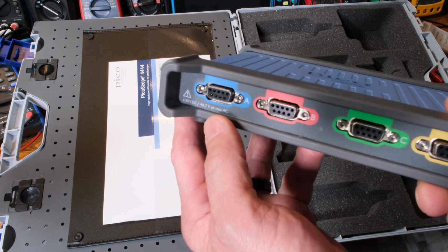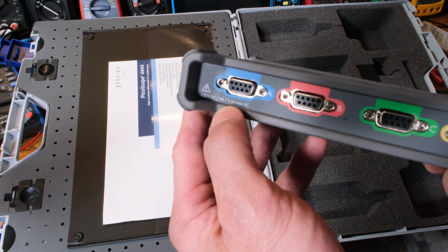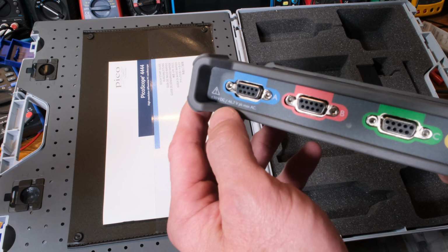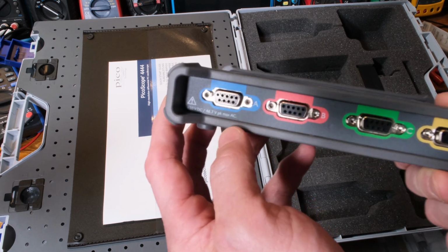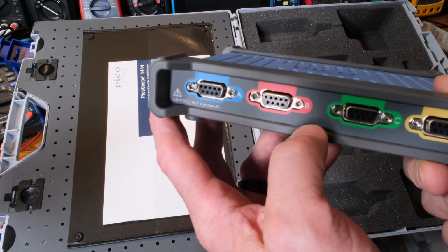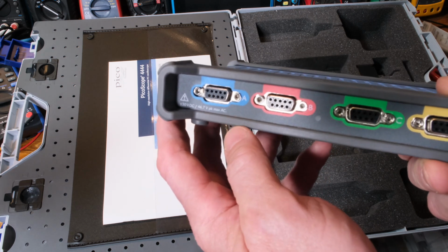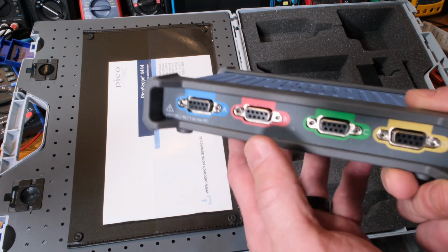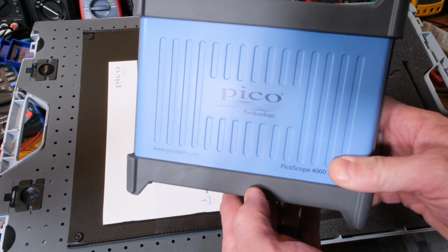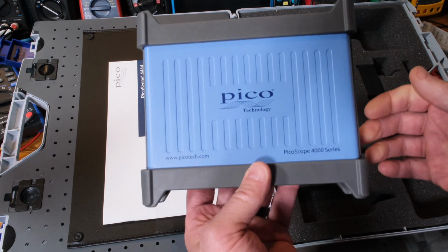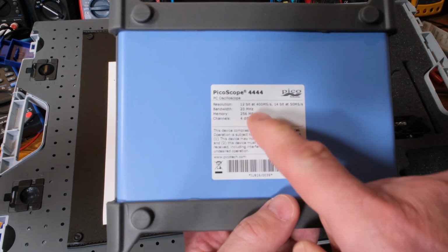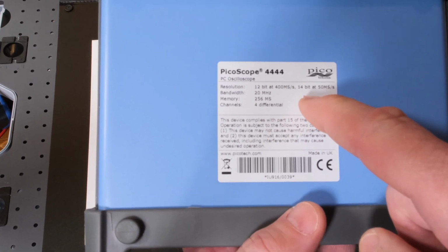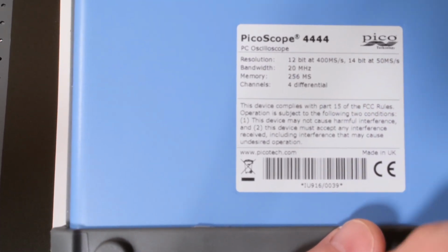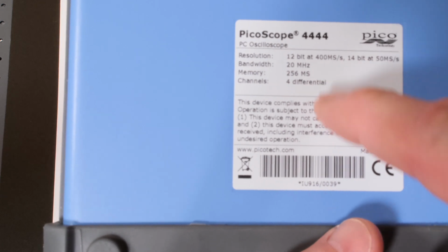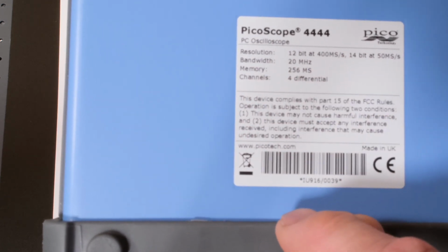And right here you can see the ratings. 46.7 volts peak max, that's at the input here, plus minus 50 volts. So if you have a ×1 probe, that's what you have to have at your end of your probe. But if you have a ×10 or ×20 or ×100, you can have higher voltage signals, of course. So right here, 12-bit, 400 megasamples per second, 14-bit, 50 megasamples per second. 20 megahertz, 256 megasamples. That's really deep memory, 4 differential channels.